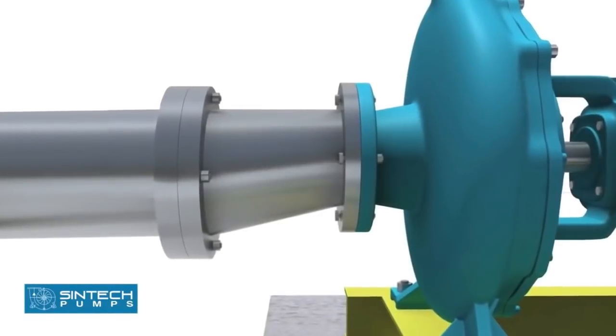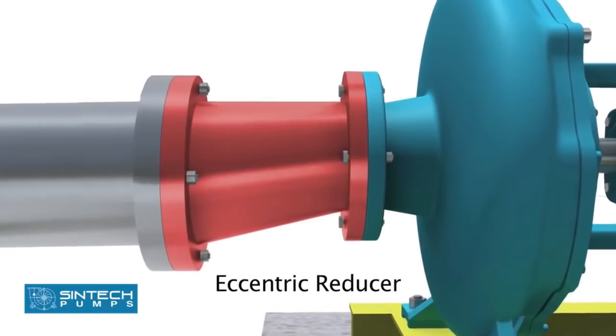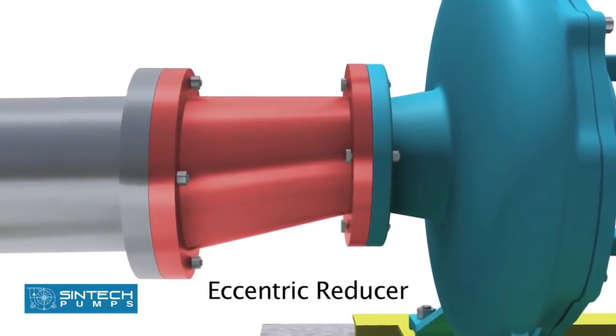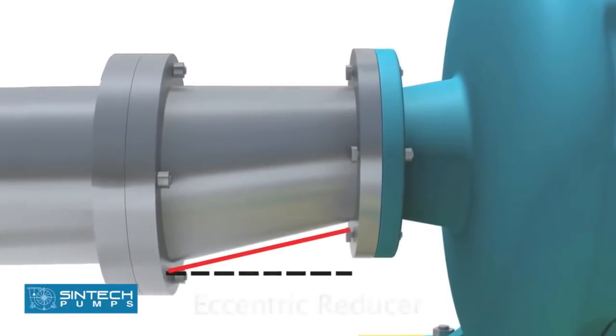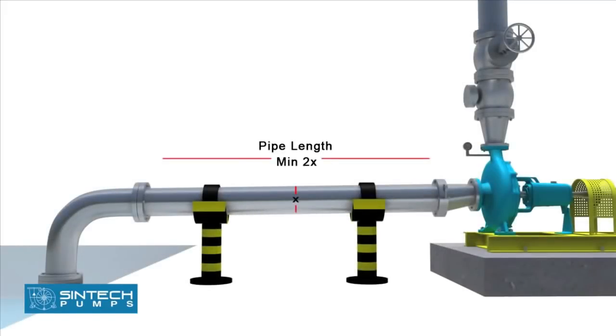The reducer joining the straight length of the pipe in the pump line should be an eccentric reducer with the inclined side of the reducer as the bottom side. The straight length of the pipe after the eccentric reducer should be two times the pipe diameter.